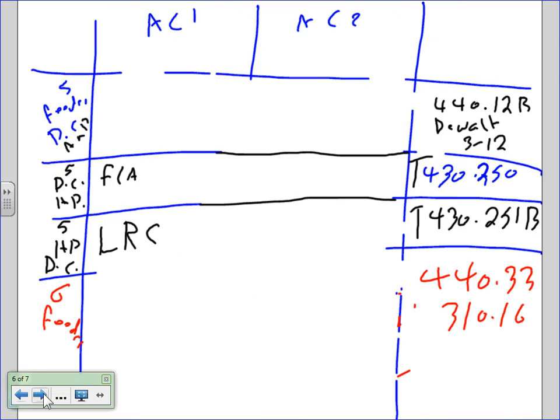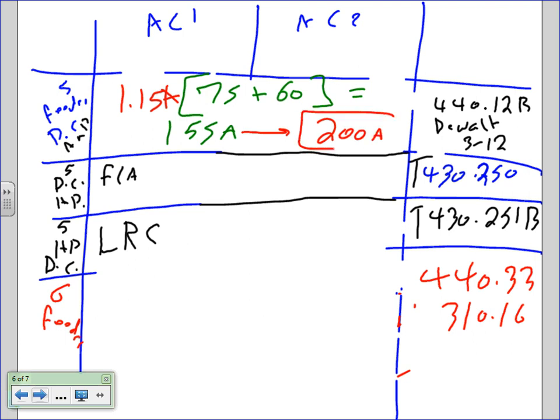Okay, let's go to feeder disconnect. The feeder disconnect, guys, we're going to size in terms of amps. So let's use this one. Here's what they say. You take 1.15, and then you multiply by the sum of 75 plus 60. You can see how you multiply by the sum of the two, and that will get you 155 amps. And if you go to the standard sizes, that will translate into 200 amps, per 440.12(B), 312. You add them up and multiply by both. That's the amp size.